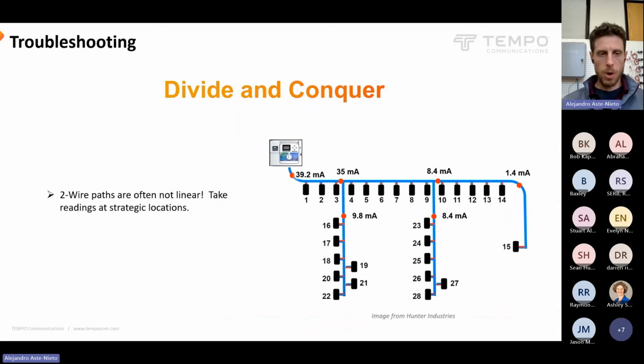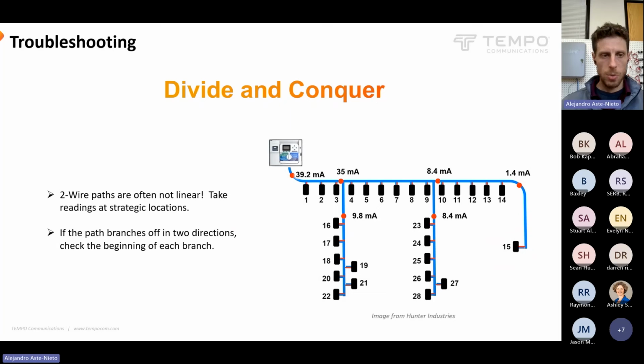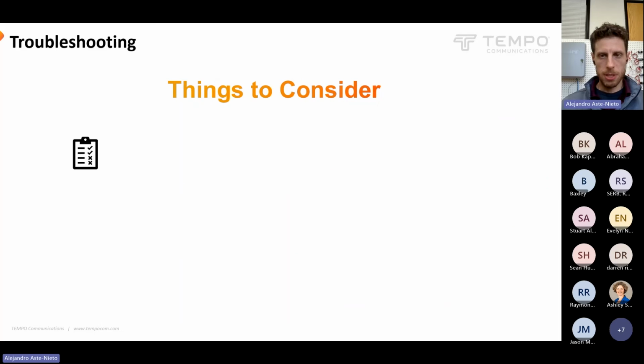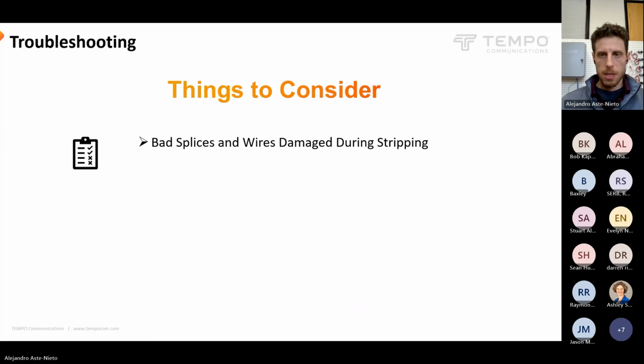So not every wire path is just a straight line, obviously. So you're going to want to take strategic measurements. Whenever a wire path branches off, take a measurement at the beginning of each branch and just see if it's the number that you expect there. And some things to consider: splices and wires damaged during stripping are typically where the problem will occur. So that's kind of what we're looking out for.